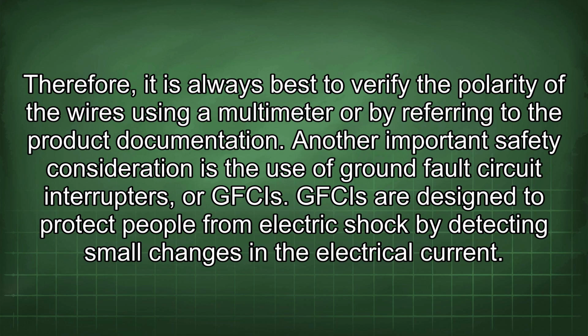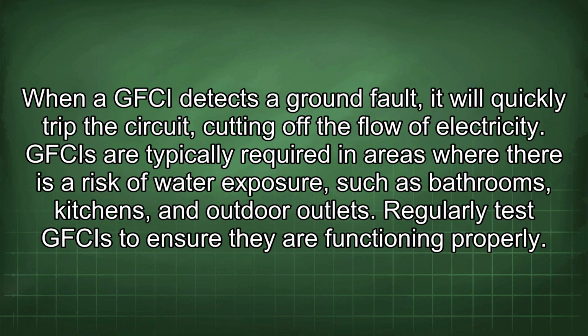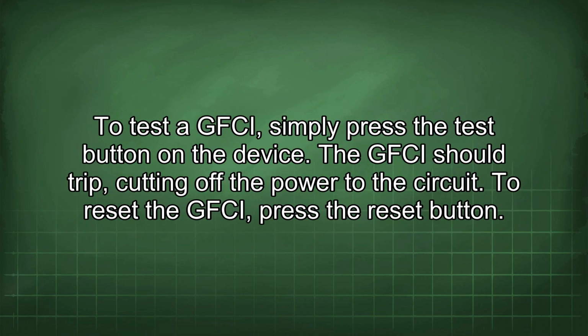Another important safety consideration is the use of ground fault circuit interrupters, or GFCIs. GFCIs are designed to protect people from electric shock by detecting small changes in the electrical current. When a GFCI detects a ground fault, it will quickly trip the circuit, cutting off the flow of electricity. GFCIs are typically required in areas where there is a risk of water exposure, such as bathrooms, kitchens, and outdoor outlets. Regularly test GFCIs to ensure they are functioning properly. To test a GFCI, simply press the test button on the device. The GFCI should trip, cutting off the power to the circuit. To reset the GFCI, press the reset button.